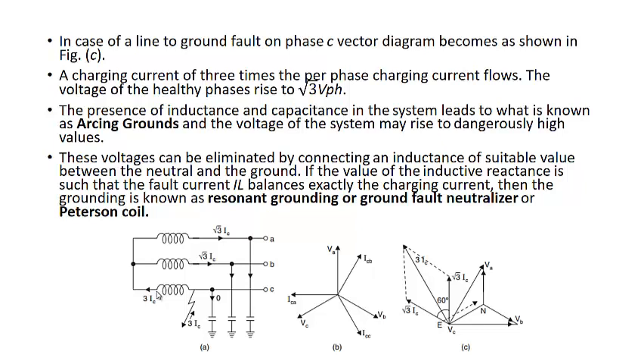There are two things that you need to understand from this discussion. One is that the disadvantage of this isolated neutral is that the phase voltages of the other phases, which are not involved in the fault, have increased to the line values. The faulty line has definitely zero voltage with respect to ground, but the other voltages will rise to the line value. That is the disadvantage of this.